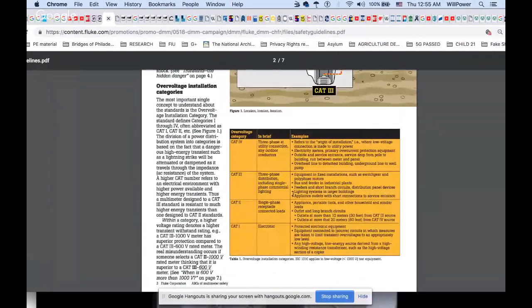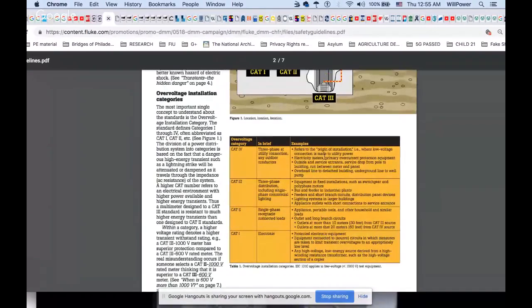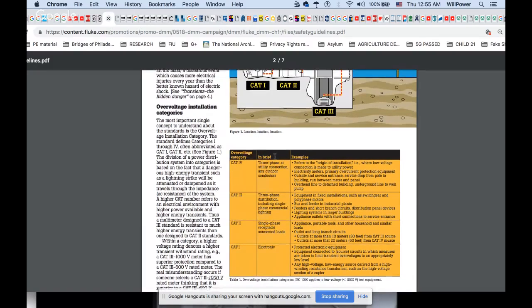So we're at Cat 3 now. Now at Cat 4, you're at the origins of installation. So now you can go to that panel, but you have to make sure that panel does not exceed 600 volts. And this is why Cat 4 is worth the extra money.